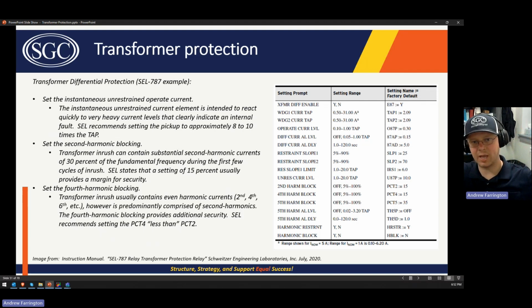And when you close back in the breaker and energize the transformer, it may be that the flux was going in this way, and then the currents, when you close in the breaker, want the flux to be going this way. And so you get that initial surge to energize the transformer. That's transformer inrush. That can contain a significant amount of harmonics. And so you want to block for those. Follow the relay manufacturer's recommendations or your client standards.